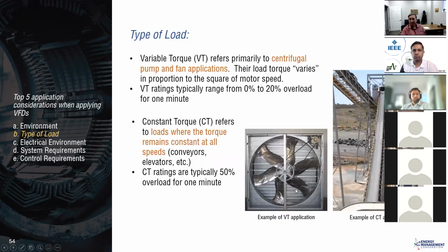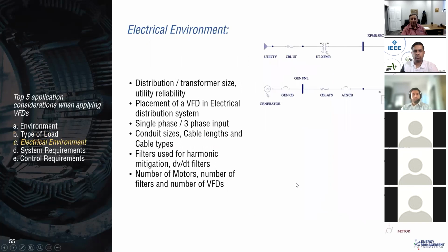Another interesting application is conveyors, which is certainly constant torque, but when you're going downhill, now you've got regeneration. And there's a good place for an active front end, where it will regenerate that load, and you do have to worry about the harmonics from that standpoint. We had an application up in Alaska where they were loading wood chips into a ship, and they were running on a standby generator. So they had to have low harmonics, they had to have regeneration, they had to have control of the conveyor, and all of those added up to an obvious way for us to mitigate harmonics and meet the load demands.